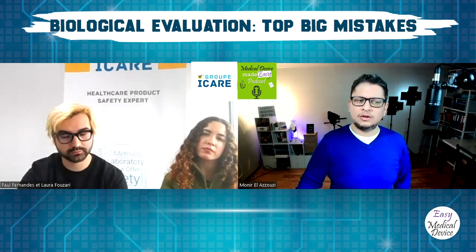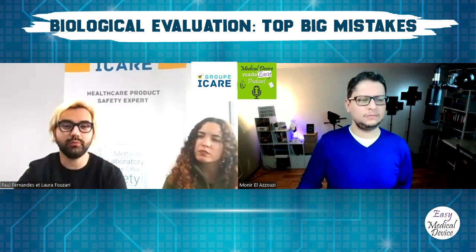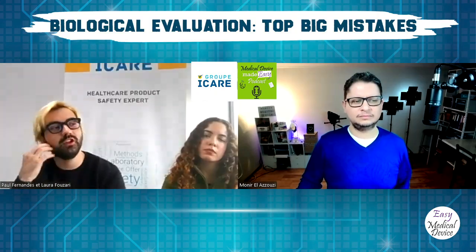Okay, are there any other issues here? I think we have maybe two little points. This is not mistakes, but it's a point that manufacturers are often not aware of, and we prefer to talk about it here so people will know. Some endpoints in the famous table of the 10993-1 are not checked in the table. It's the case for degradation, reproductive toxicity and developmental toxicity.